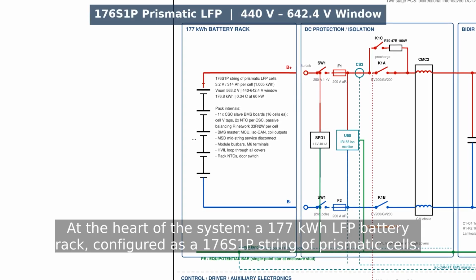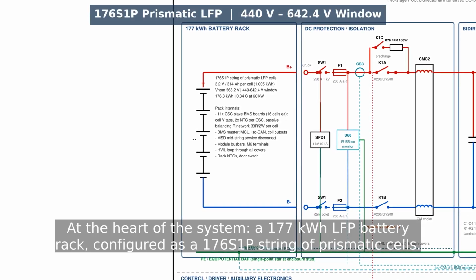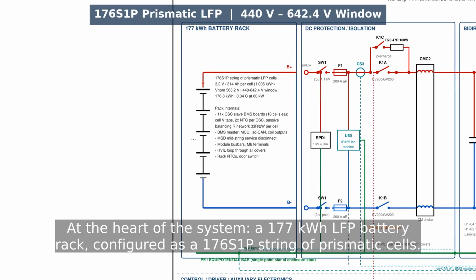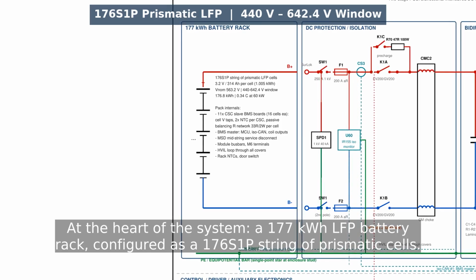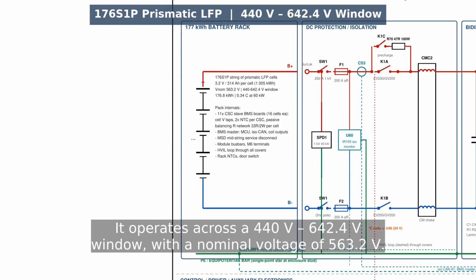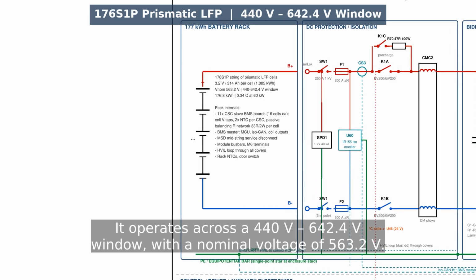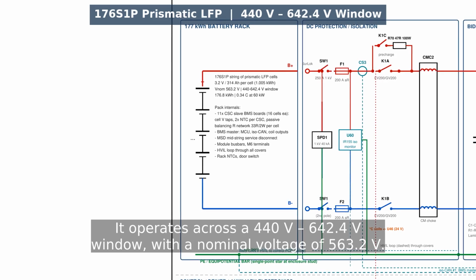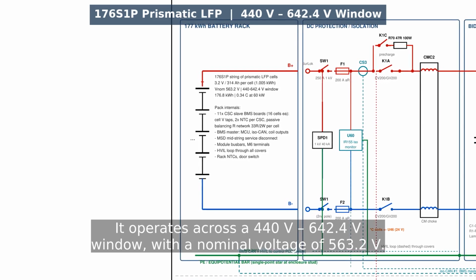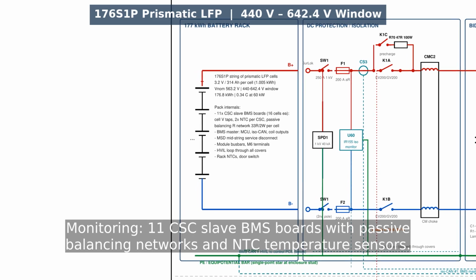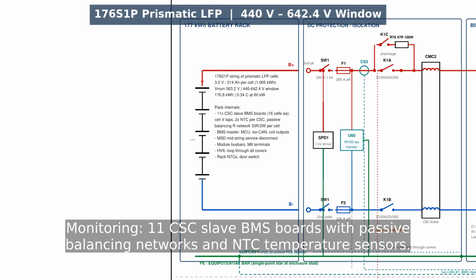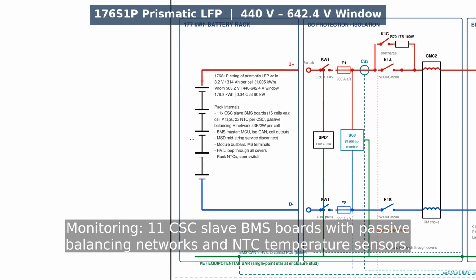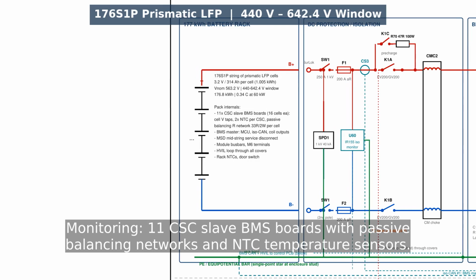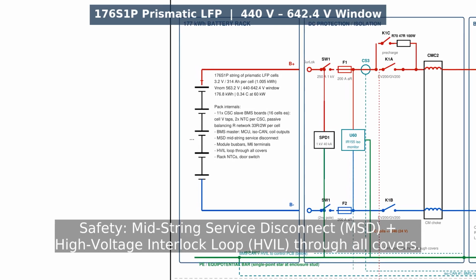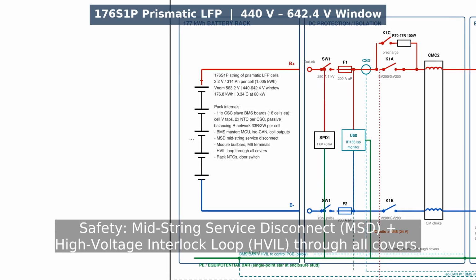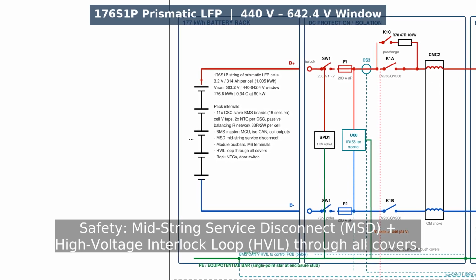177 kilowatt hour LFP battery rack, configured as a 176S1P string, using prismatic cells. It operates in a voltage window of 440 to 642.4 volts, with a nominal voltage of 563.2 volts. Internal monitoring is managed by a master and slave BMS featuring passive balancing networks and NTC temperature sensors for safety. The rack incorporates a mid-string service disconnect and the high voltage interlock loop running through all connectors.